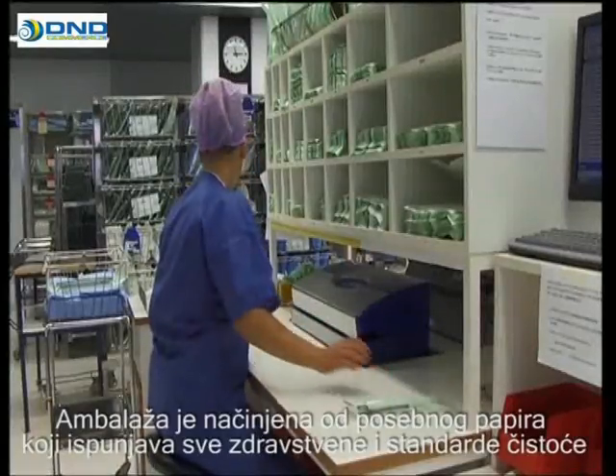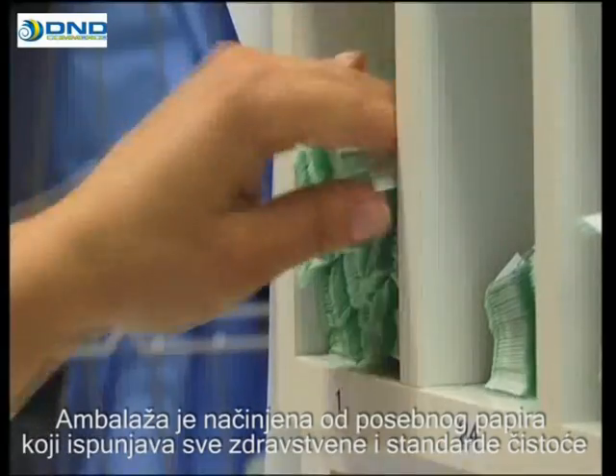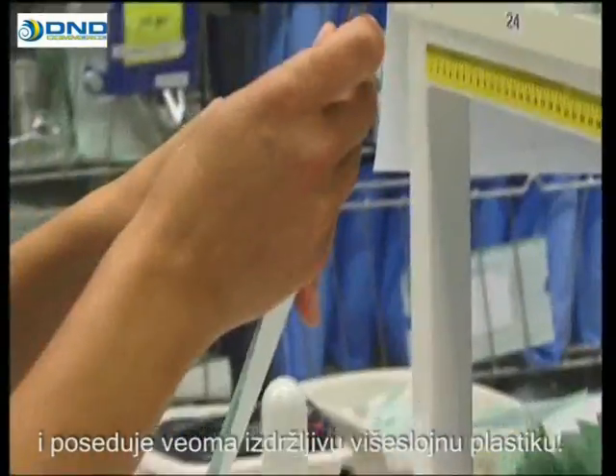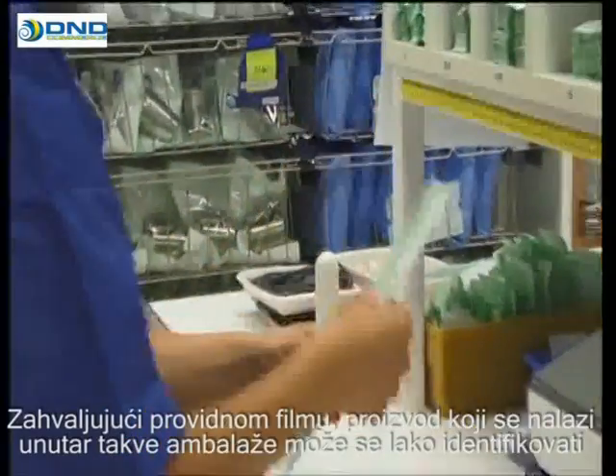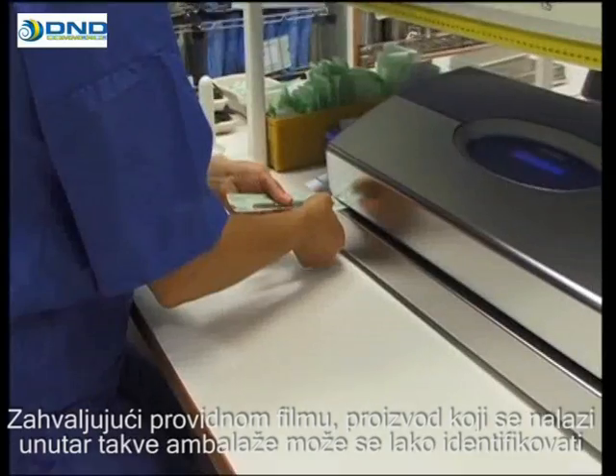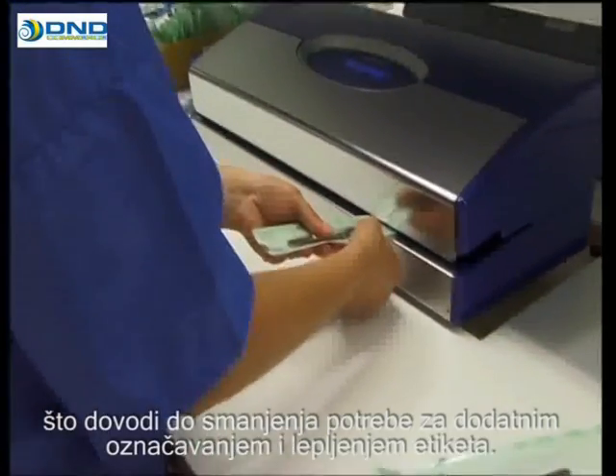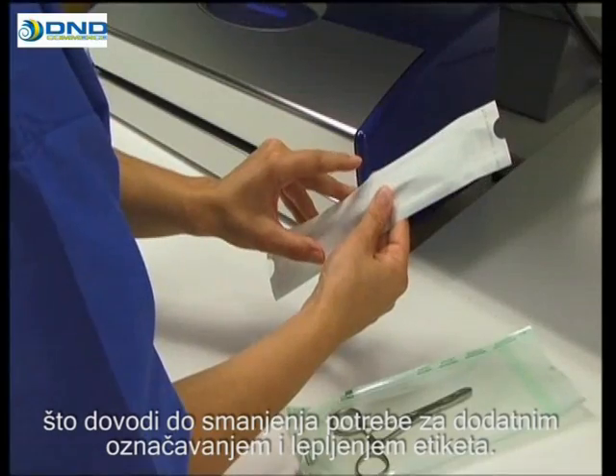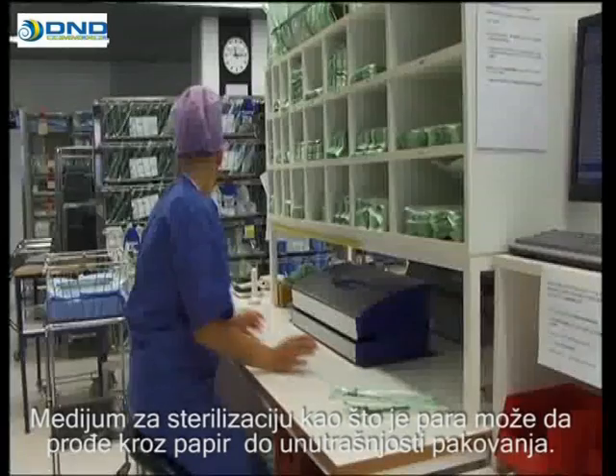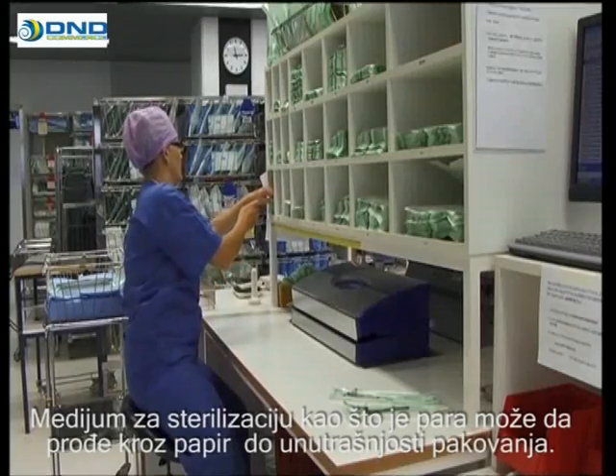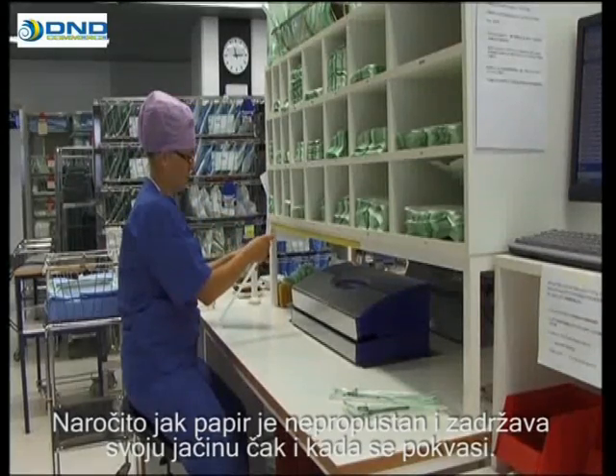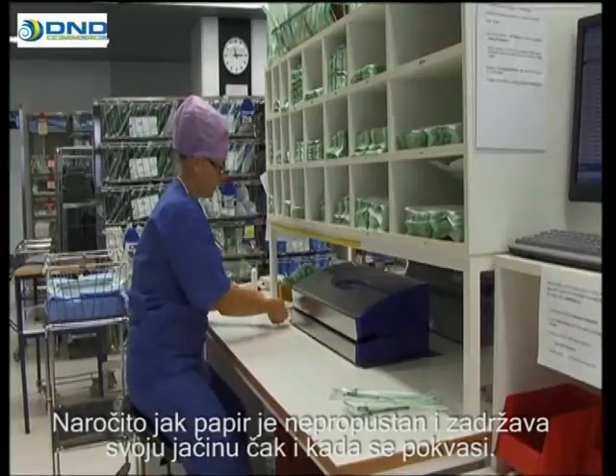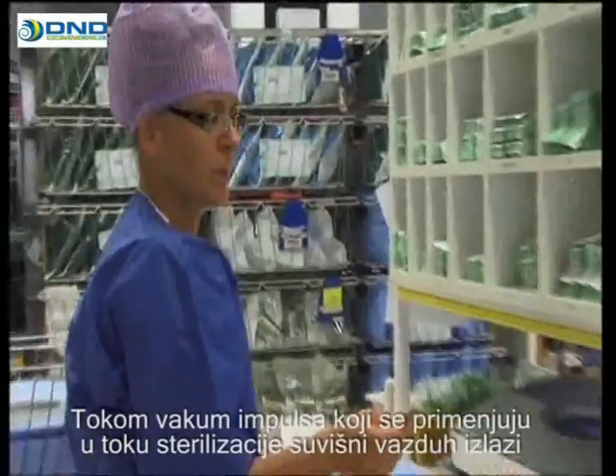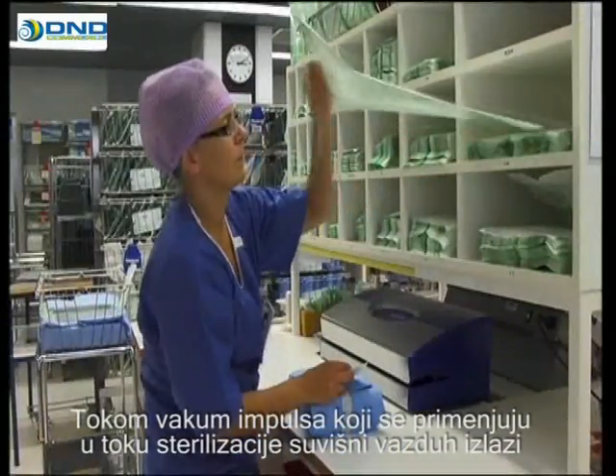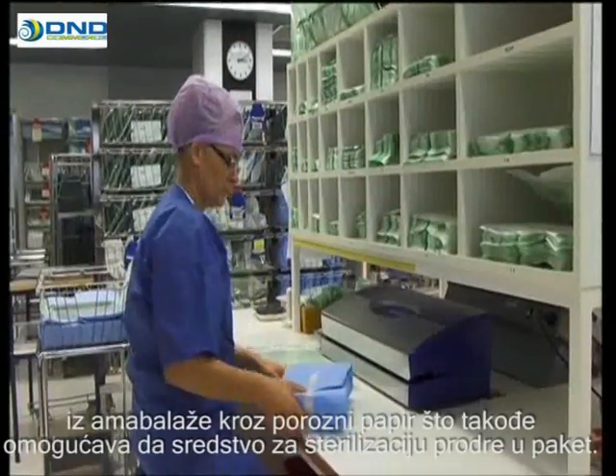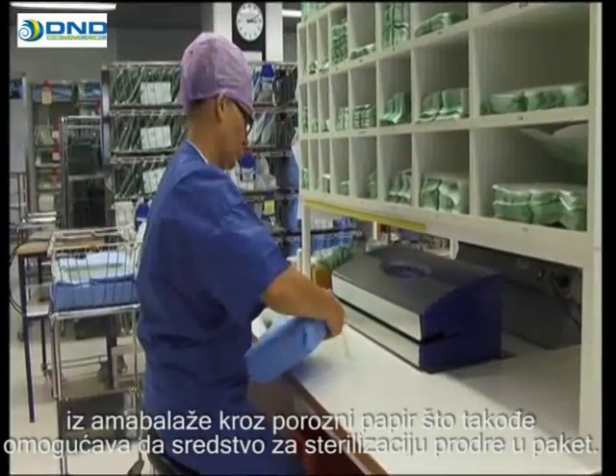The packaging is made from special paper, which meets healthcare purity and quality standards, and a highly durable multi-layer plastic film. Thanks to the transparent film, the products inside the packaging can be easily identified, therefore reducing the need for additional marking and labeling. The sterilizing medium, such as steam, will penetrate through the paper to the inside of the package. The exceptionally strong paper is waterproof and maintains its strength even when it's wet. During the vacuum pulses applied in sterilization, excess air escapes from the package through the porous paper that also enables the sterilizing medium to pass into the package.